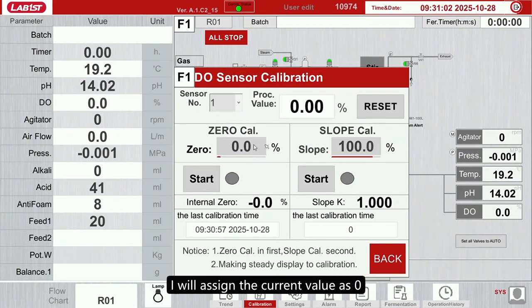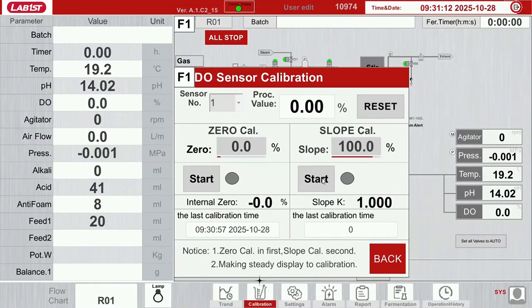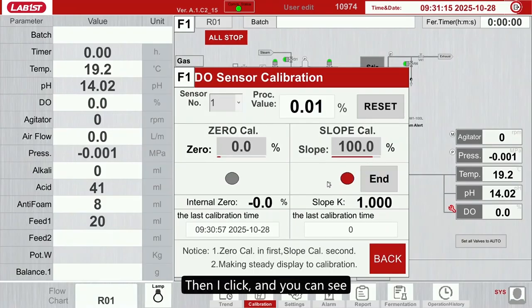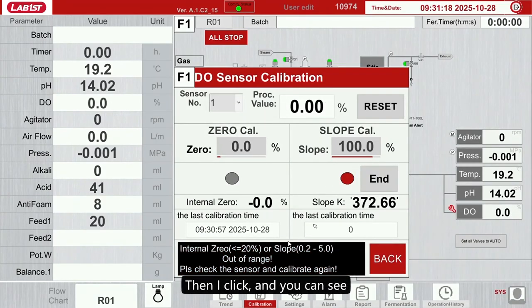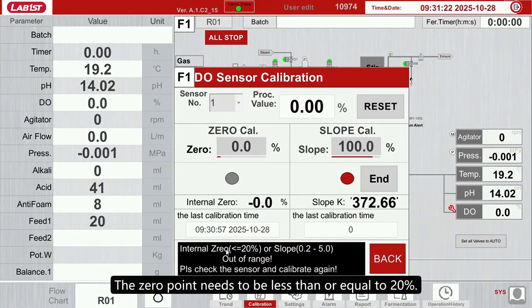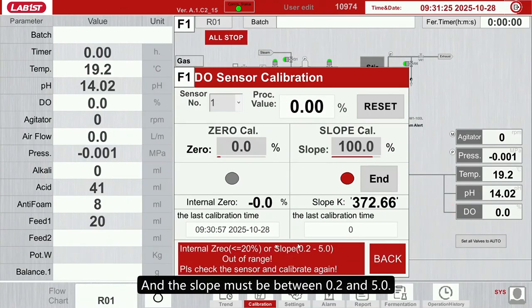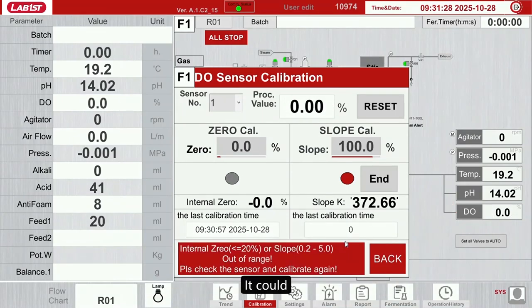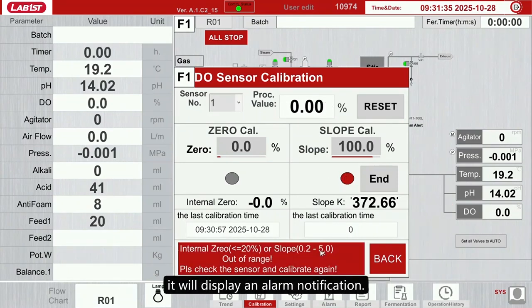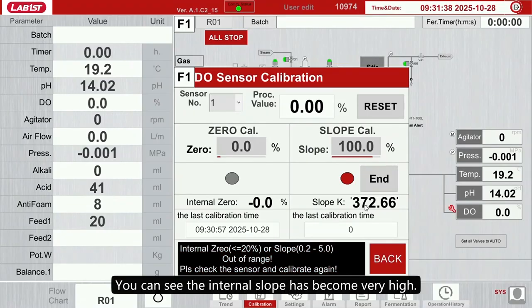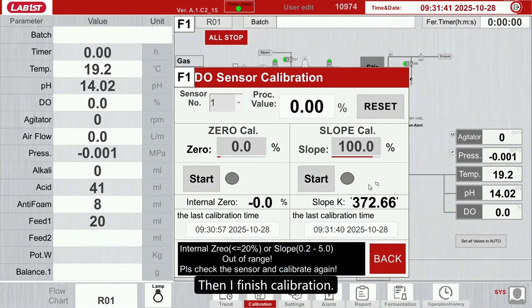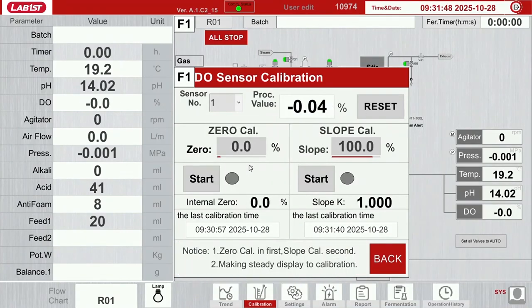I will assign the current value as 0, then the slope, as there is no electrode. So it remains at 0. Then I click and you can see the 0 point needs to be less than or equal to 20%. And the slope must be between 0.2 and 5.0. It could be within a normal range. When a value exceeds the normal range, it will display an alarm notification. You can see the internal slope has become very high. Then I finish calibration. Because the calibration failed, you need to click Reset. Then recalibrate it.